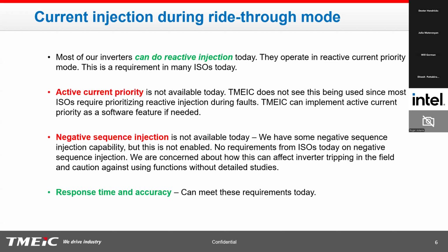We would have to wait for some ISO requirements to see what the ISO specifically wants during fault events. For example, ERCOT prefers reactive injection during fault events. CAISO has a very specific statement that they need a certain level of reactive injection during fault events. So we don't see this being widely adopted by ISOs. So reactive injection is always being prioritized. While it is a software change that we can implement, we think that most people would be using reactive injection. When it is required by certain ISOs, we would be developing that function, but we don't have that available today.